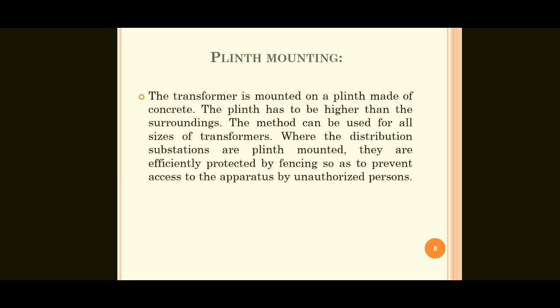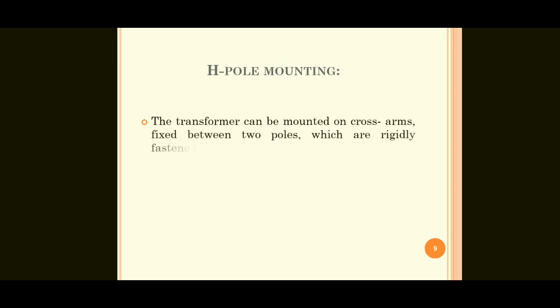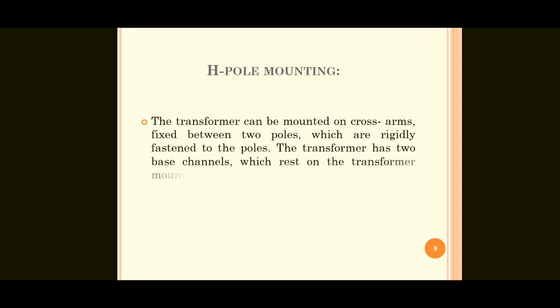Where the distribution transformers are plinth mounted, they are efficiently protected by fencing so as to prevent access to the apparatus by unauthorized persons. Next one, H-pole mounting. The transformer can be mounted on cross arms fixed between two poles which are rigidly fastened to the poles. The transformer has two base channels which rest on the transformer mounting structure.